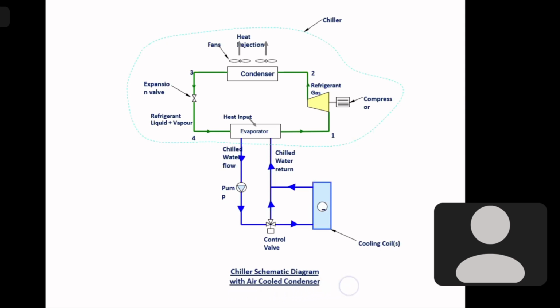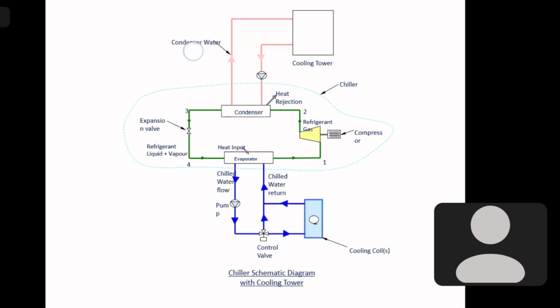A chilled water system can again be of two types. One is the air-cooled chilled water system, where the condenser is cooled by air. There is another system, the water-cooled chilled water system, where the condenser is cooled by water. So we'll see it in the next slide. Please go to the next slide. Yes. Everything is the same again as the previous one, only in the condenser part we cool the condenser by water. The condenser is again a shell and tube heat exchanger.